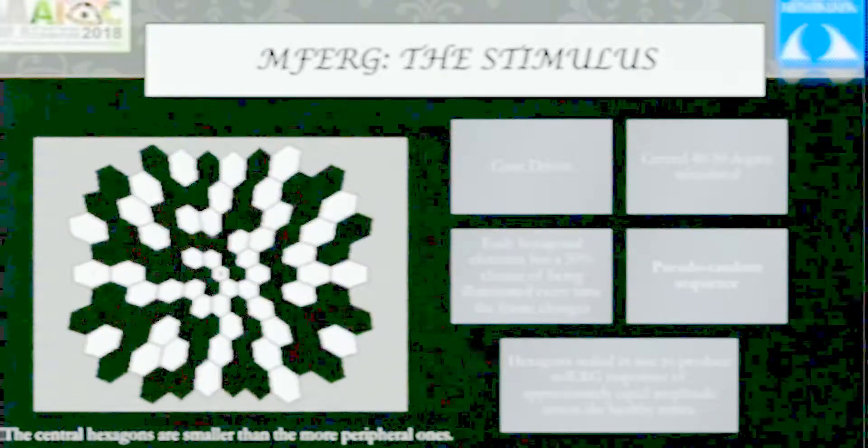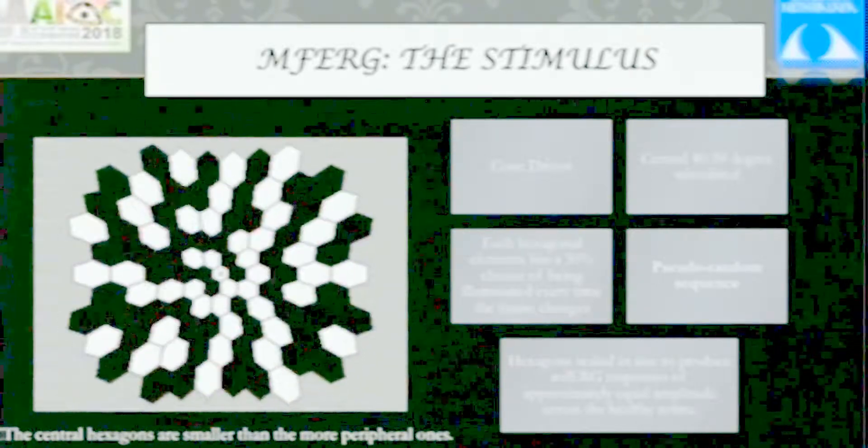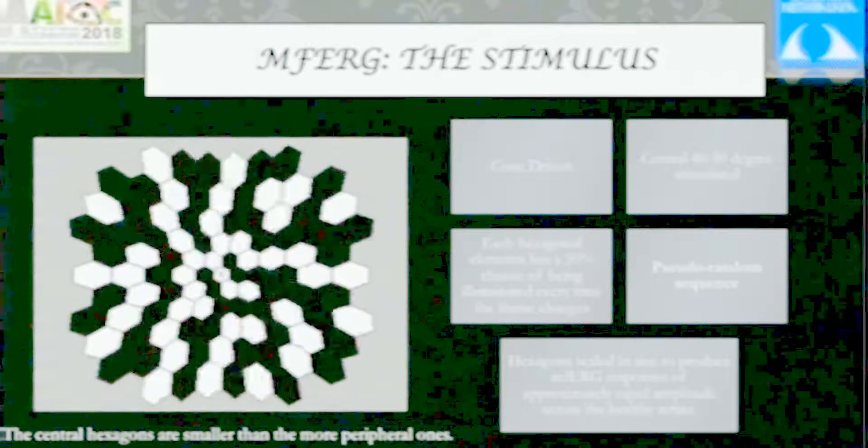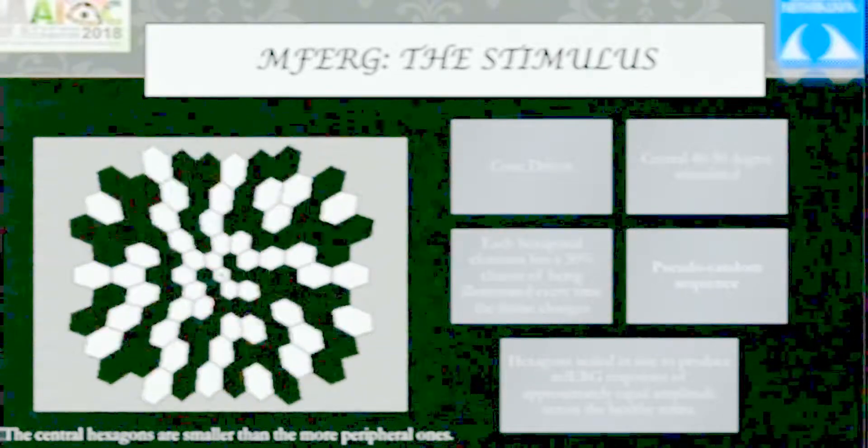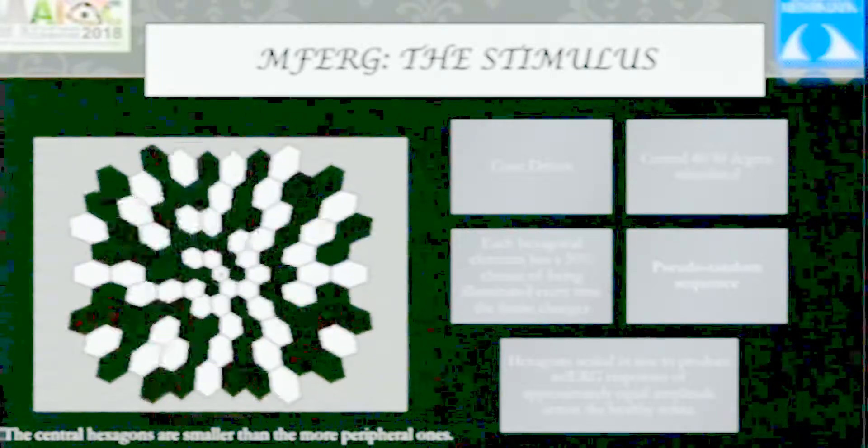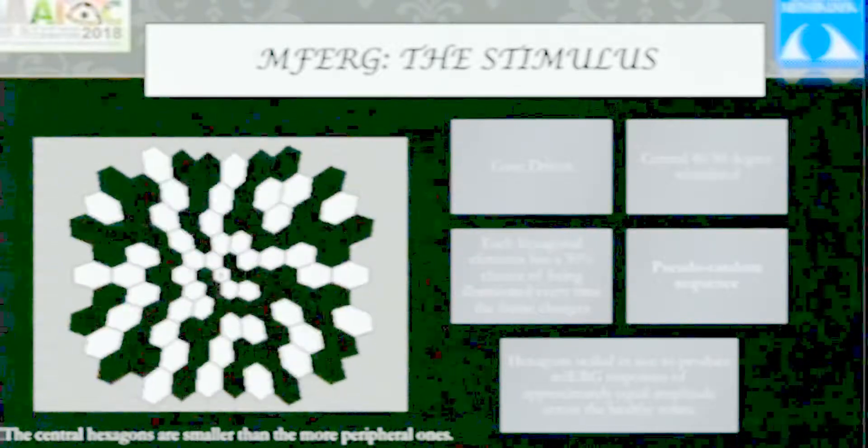This is the typical stimulus for multifocal ERG. It may appear to be randomly flickering light, but it's called a pseudo-random stimulus because the flicker happens according to a particular M-sequence fed into the software. At any particular time, almost 50% of the hexagons are illuminated and 50% are dark. The size of the hexagons is measured - central hexagons are very small while peripheral ones are larger. This is because the central area has a larger number of cones, so we want equal numbers of cones represented in each hexagon.